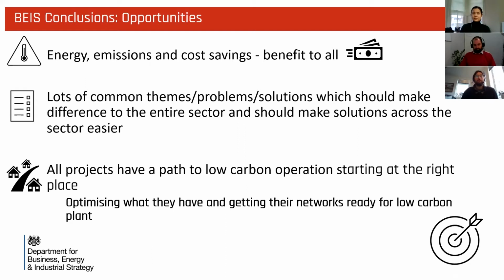And I think another part to this is that all the projects that we've looked at now, if they do choose to take on the findings and the recommendations from the reports, have a path to net zero, or at least a path to low carbon operation. And it's done in what seems to be the sensible way round, if I'm allowed to use such a term, where you look at what you've got first, you optimize that, you reduce the operating temperatures and requirements, and then you're ready for any other plant that you want to put in, rather than just going straight for some low carbon plant without addressing some of the fundamental system-based issues.